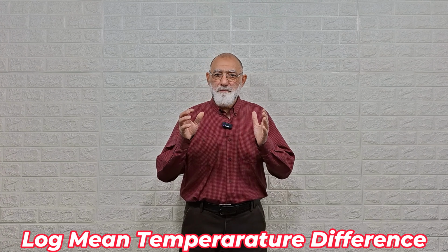In engineering terms, this phenomenon is the decrease of the LMTD, logarithmic mean temperature difference indicator. Since this average indicator is low in R407C, the cooling weakens.